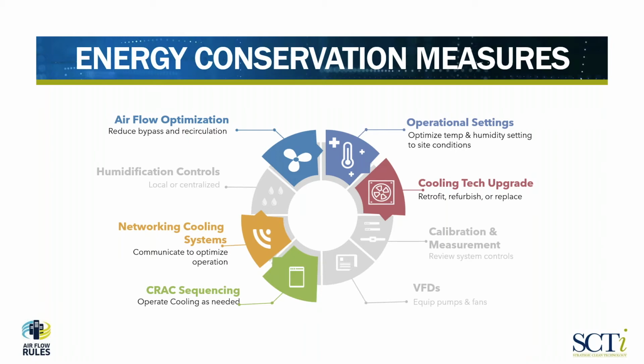Tied in with that, of course, depending upon the vintage of the crack units as well, we look at doing cooling tech upgrades. Again, information on our website is available on that, which we refer to as a floating head retrofit. And that's taking a slightly older version crack unit and replacing some of the original components with new components, which are being used in the newest crack units on the market, and making that unit operate more efficiently. And here we've seen considerable energy savings, and to date we've done over 225 crack units with that floating head retrofit, and it's been extremely successful.